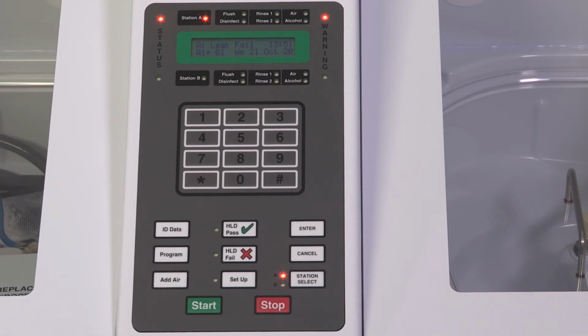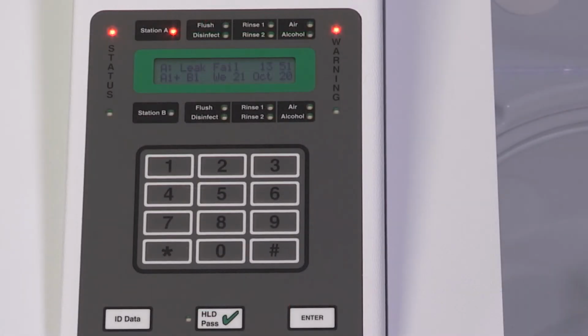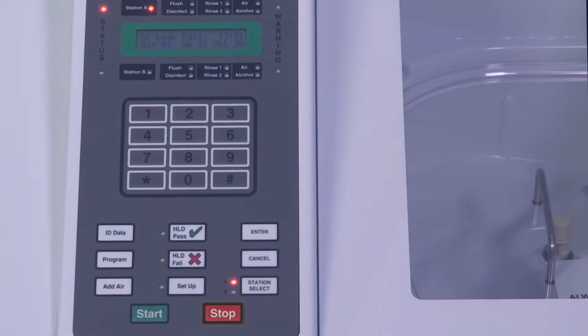If there is a major or gross leak detected where the pressure cannot be maintained in the endoscope, the reprocessing cycle halts. The control panel's warning LED indicator lights blink, and on the screen, a leak fail error message displays. On the control panel, press Stop to end the cycle.